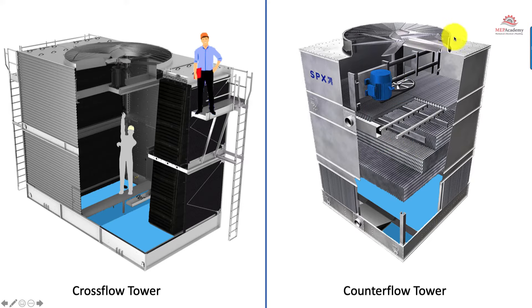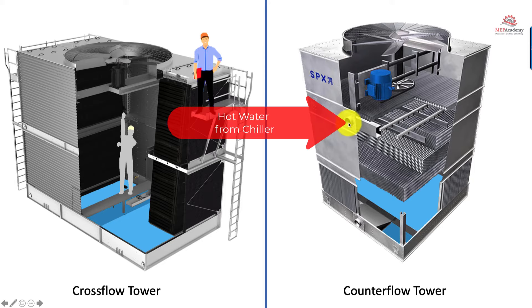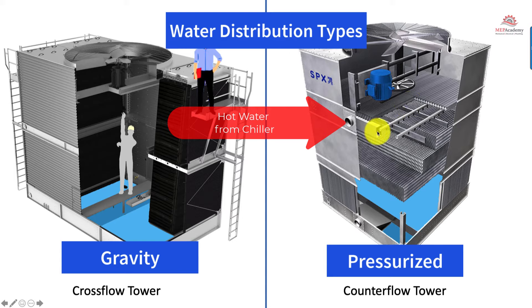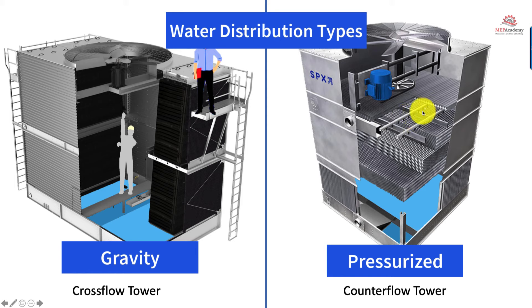Hot water comes from the chiller and enters the tower. There are two water distribution types: pressurized and gravity. On a counter flow it's pressurized — the hot water comes in, goes through the distribution header and into the distribution pipes, and through the nozzles it's sprayed out over the fill.